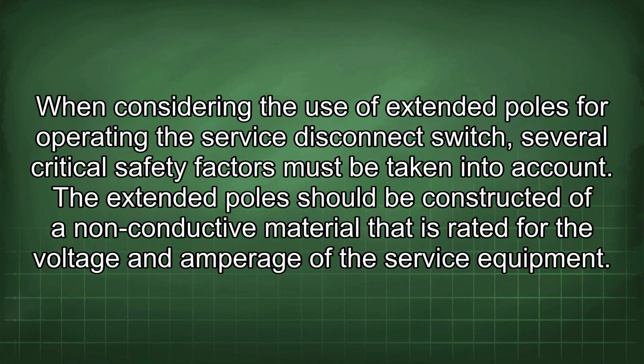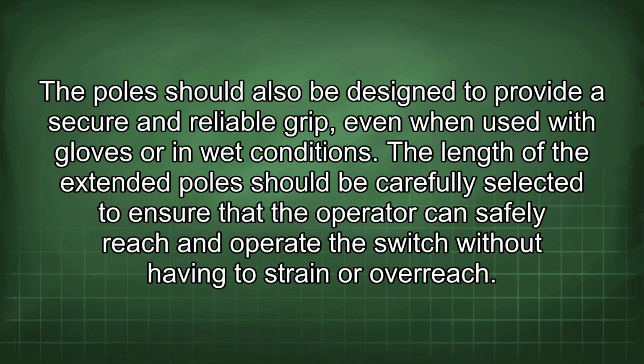When considering the use of extended poles for operating the service disconnect switch, several critical safety factors must be taken into account. The extended pole should be constructed of a non-conductive material rated for the voltage and amperage of the service equipment. The pole should also be designed to provide a secure and reliable grip, even when used with gloves or in wet conditions.